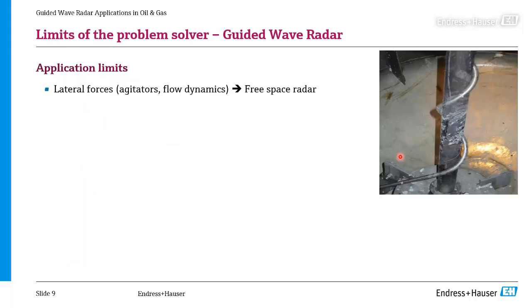There are also limitations we have to admit. Whenever you have lateral forces, like you can see in this picture here, you have an agitator and the guided wave rod was too close to the agitator, then it just flipped around this agitator. Things like this can happen, so you have to be careful whenever you have an agitator. Think of going free space. Or also, if you know you have a lot of flow dynamics in a tank or in a vessel, then you should also think of going free space radar, or at least contact your Endress+Hauser salesperson to be sure that this application will work then.